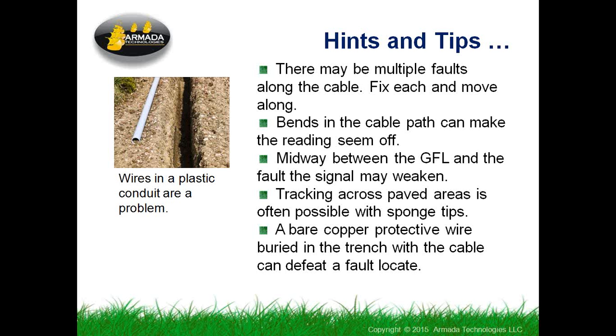You may lose the signal along the cable, in which case you need to keep going. Even if we're getting a good kick out of a fault, the ripples may not be strong enough if the fault is way down the cable. Remember that these ripples are spreading out into the earth, dissipating and spreading across the earth and rejoining at the ground stake. And when that's happening, they're pretty weak where they've spread out the most. But as you approach the fault, you'll pick up the signal again.